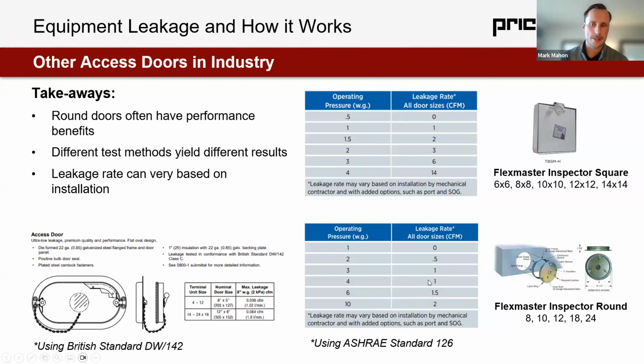And that's why testing is sometimes a benefit in the field as well. If you install a great door, but don't install it correctly, it can still leak. So round doors are better. That's one takeaway. The other interesting takeaway is that there are very different test methods here. ASHRAE Standard 126 for FlexMaster doors is a leakage test that only looks at the door by itself. Essentially, the mate of the door to the ductwork is very built up to assure that we're only looking at the door.